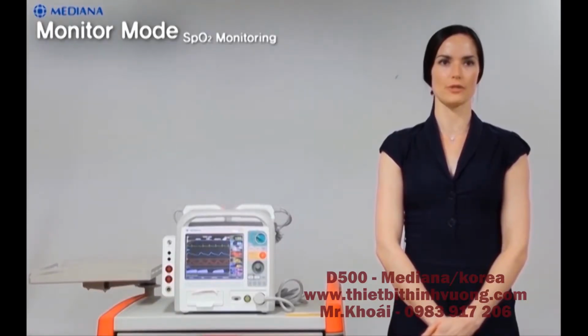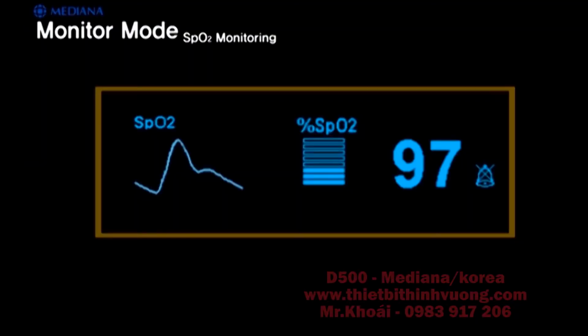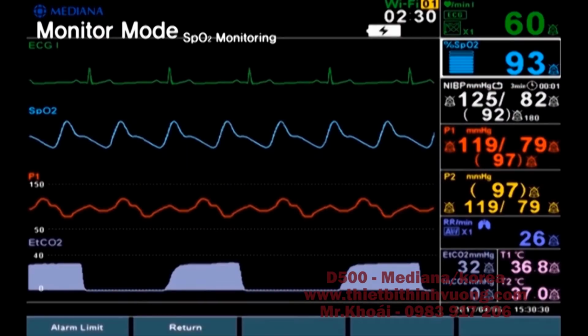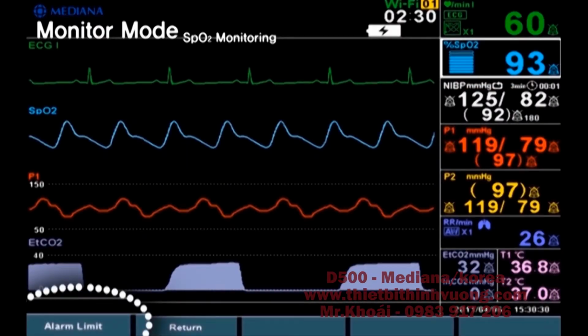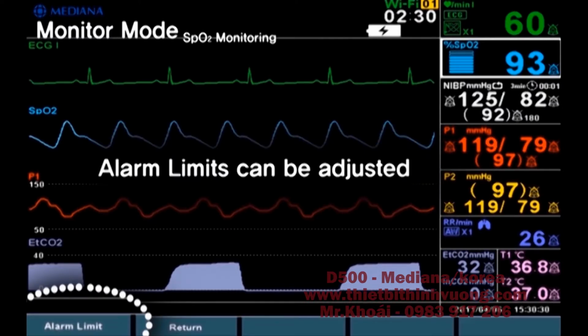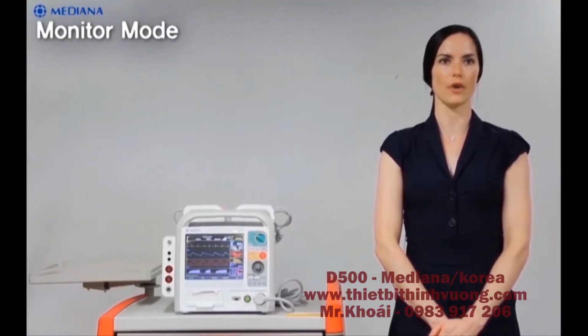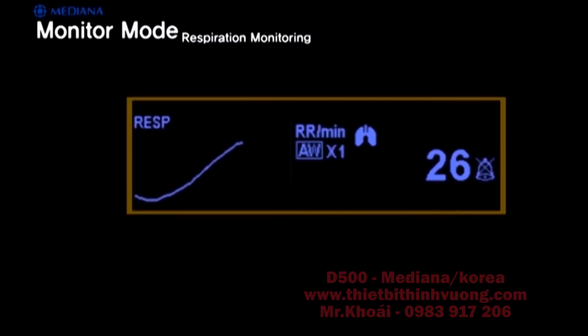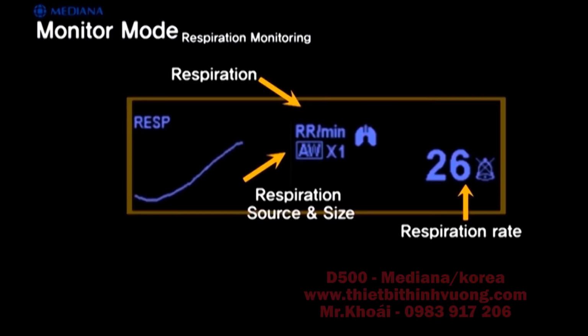Next, to SPO2 monitoring. Here you can see how the SPO2 measurements are presented on the screen. In the SPO2 menu, we only have the alarm limit settings. Number 1, the alarm limit can be adjusted. Now, let's move on to respiration monitoring. Here you can see how the respiration measurements are presented on the screen.